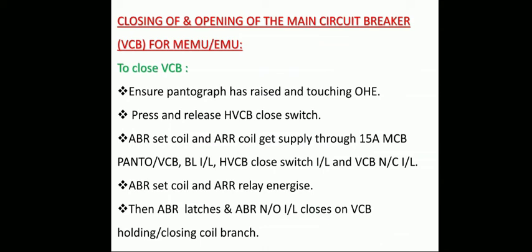To summarize how VCB closes: ensure the pantograph has raised and is touching the OHE, then press and release the HVCB close switch. The ABR set coil and ARR coil will energize through the 15-amp MCB for pantograph and VCB, BL interlock, HVCB close switch interlock, and VCB normally closed interlock. The ABR set coil energizes and latches, with its normally open interlock closing on the VCB holding and closing branch.